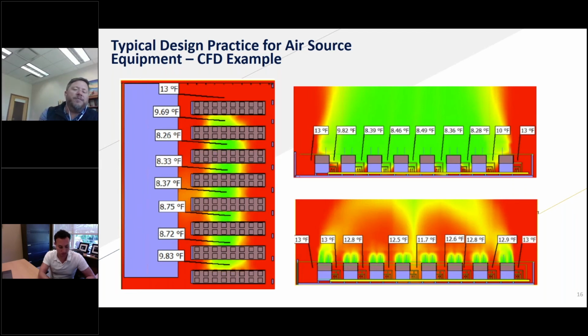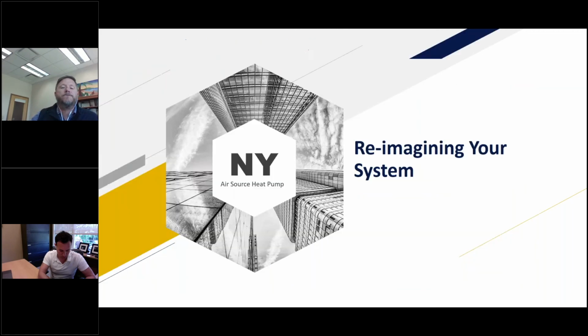So again, just pointing out, this is something that we're not typically used to, because normally we might have a cooling tower or cooling towers on the roof. You do have to think about this, but they have a different footprint form factor than air source heat pumps do. Same thing with air cooled chillers. Typically, we're not having as many of those on a roof as we're going to be having with an air source heat pump. And so again, it's something that definitely needs to be considered, especially when you think about warm air rises, cold air likes to stay below. So it's just a factor that sits there, and we get that recirculation of that cold air. So I'm going to move on.